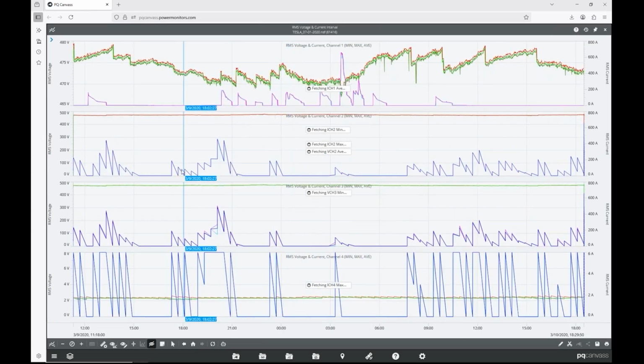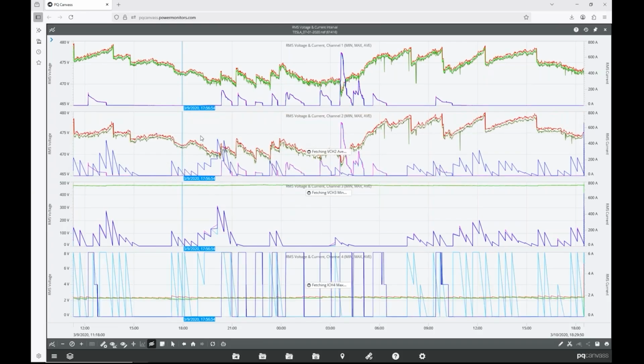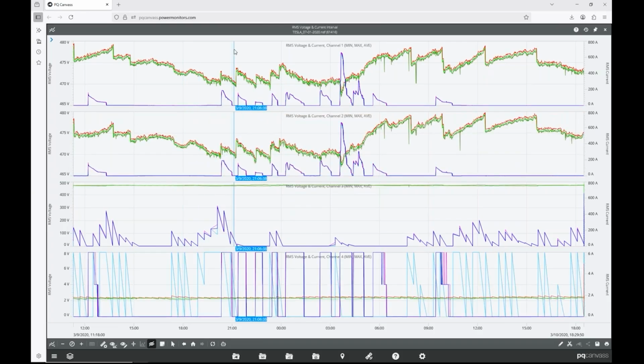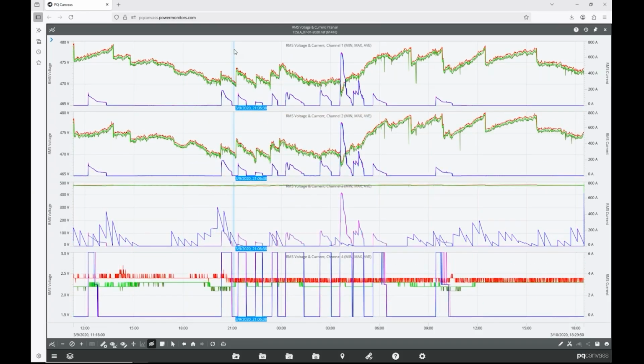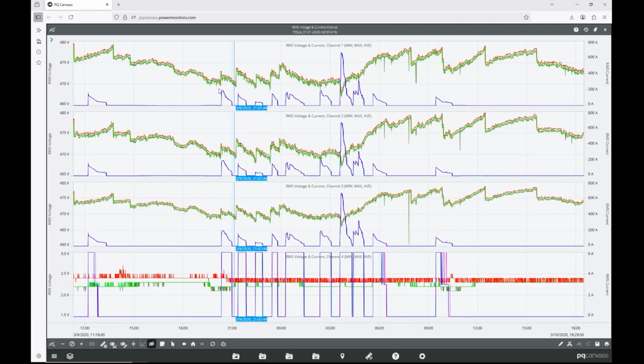You see these kind of sawtooth or triangle wave patterns where the current abruptly increases, and that can be a step change in the voltage, but then the current ramp down is more gradual. Now you can see that the voltage wasn't affected that much. There are times when the voltage does change at roughly the same time, maybe not exactly the same time. Some of these are regulator adjustments, but other times the voltage is not affected. In this site, this is a fairly large transformer that is somewhat resistant to the changes in voltage.